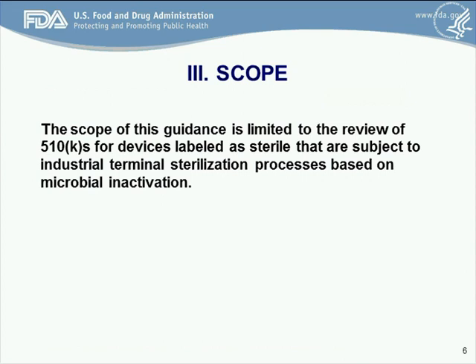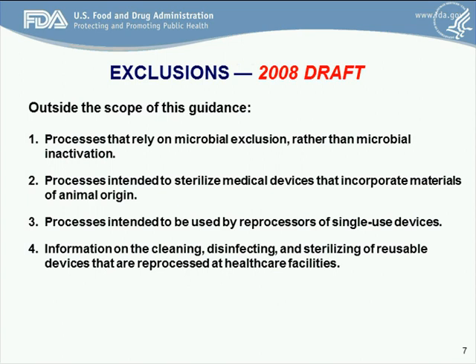The scope of this guidance is limited to the review of 510K for devices labeled as sterile that are subject to industrial terminal sterilization processes based on microbial inactivation. Outside the scope of the guidance document are processes that rely on microbial exclusion rather than microbial inactivation — examples include filtration and aseptic processing. Other exclusions include processes intended to sterilize medical devices that incorporate materials of animal origin, processes intended to be used by reprocessors of single-use devices — there's a separate guidance document for that — and information on cleaning, disinfection, and sterilization of reusable devices reprocessed in healthcare facilities, which also has a separate dedicated guidance document.